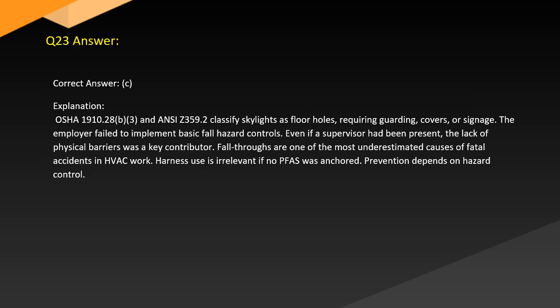Correct answer, C. OSHA 1910.28(b)(3) and ANSI Z359.2 classify skylights as floor holes requiring guarding, covers, or signage. The employer failed to implement basic fall hazard controls. But even if a supervisor had been present, the lack of physical barriers was a key contributor. Fall-throughs are one of the most underestimated causes of fatal accidents in HVAC work. Harness use is irrelevant if no anchor point was used. Prevention depends on hazard control.